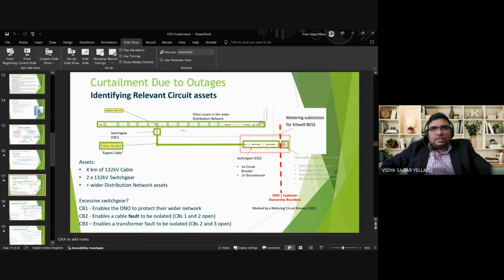This wider network, as said, is 132 kV and it has many pylons here. This generator is getting connected to this part of the wider network. So this is the cable associated with this project. It has a switchgear here and a switchgear here. If there is a fault here, then it cannot export power, so it has to be curtailed. If there is planned maintenance of this switchgear, or of the switchgear associated with this generator, it has to stop generation. It leads to curtailment. So this can be accounted for in the estimation of curtailment for this project.